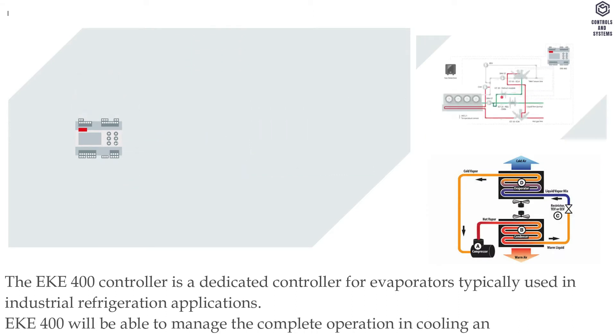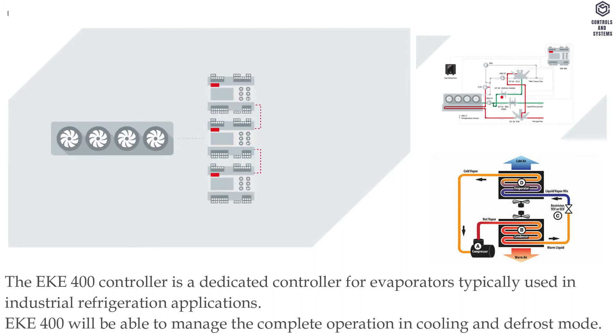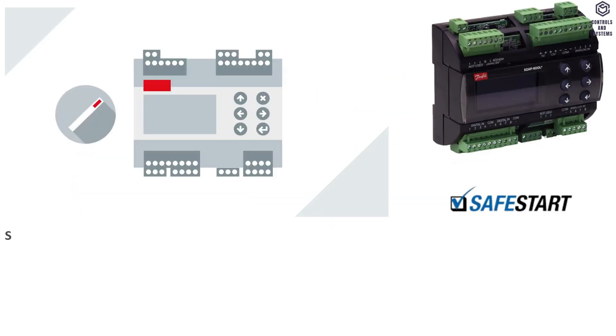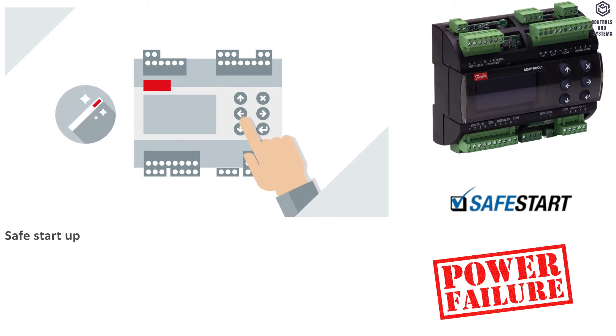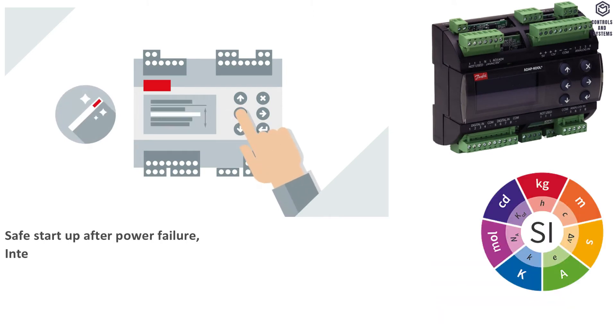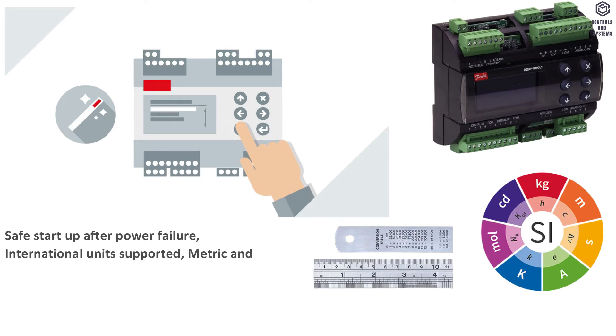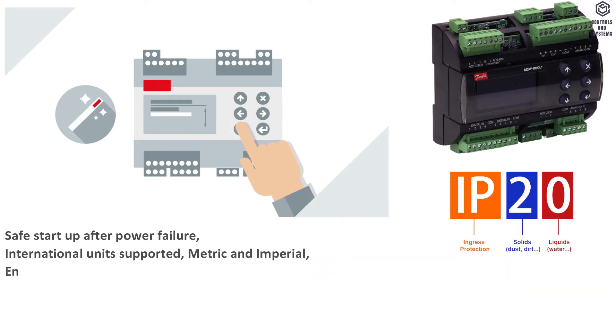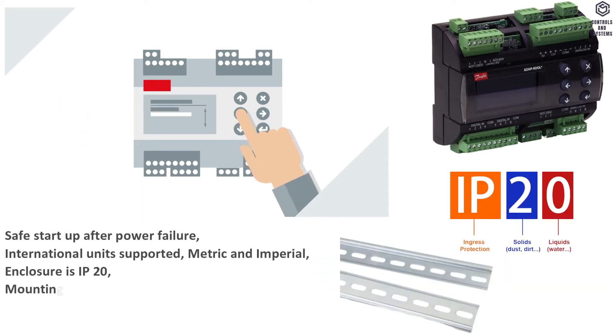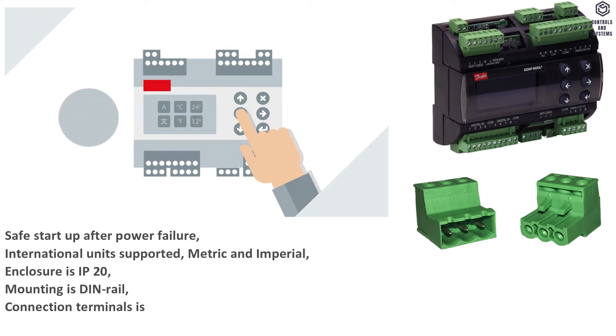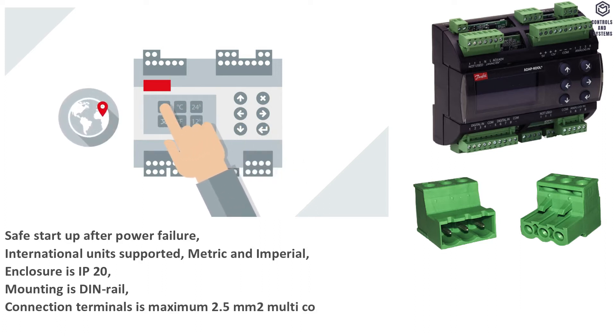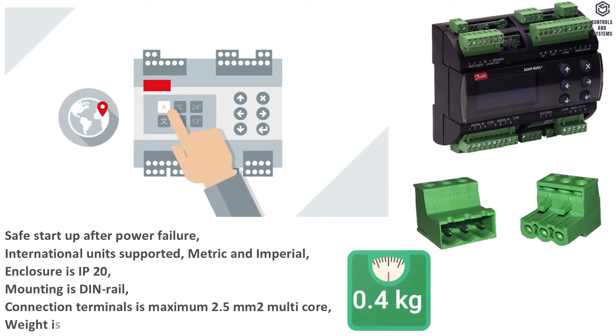The EKE400 will be able to manage the complete operation in cooling and defrost mode, with safe startup after power failure, and international units supported — metric and imperial. The enclosure is IP20, mounting is DIN rail, connection terminals accept maximum 2.5 square millimeters multi-core, and the weight is 0.4 kilograms.